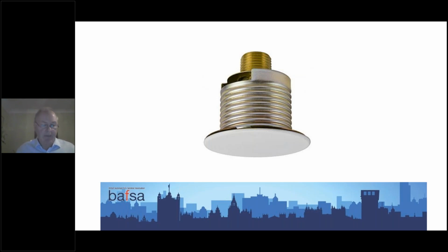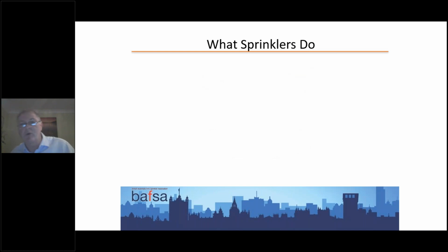So what do they do? I see some people already know quite a bit about it, but some don't. They are an independent heat-seeking element that sits in a range of pipework. The one shown earlier will operate around 67 degrees. The liquid will expand, the glass will break, and the water will then be released. Contrary to what you see in some programs, only one head will operate at a time. Another sprinkler head will only operate when it reaches, in this case, that 67 degrees.